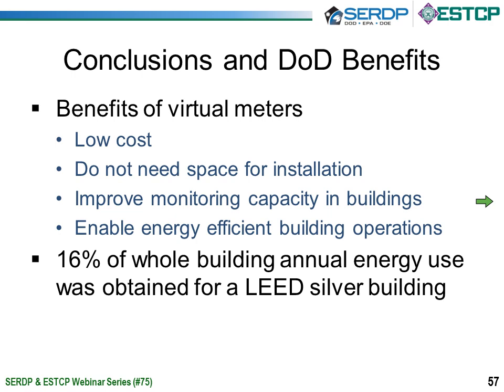By the way, I never got back to state that any of these flow rate measurements can be converted into energy flow measurements by adding measurement of the temperature difference between upstream and downstream for the medium. So for the water flowing through or the air flowing through a fan. So it improves monitoring capability. In turn, it enables providing energy efficiency by keeping the equipment operating in ideal conditions. And in this case, overall, we've measured a 16% savings on whole building annual energy use. And this was for a LEED Silver building.